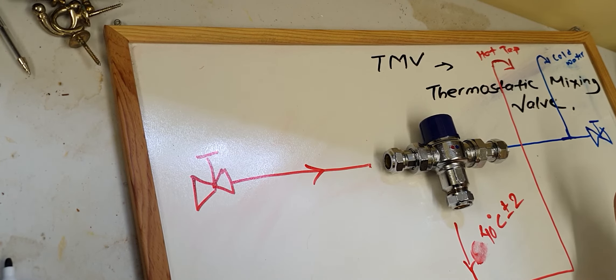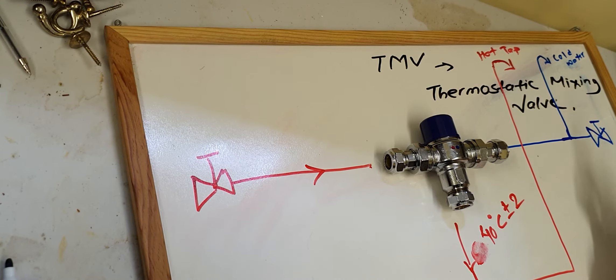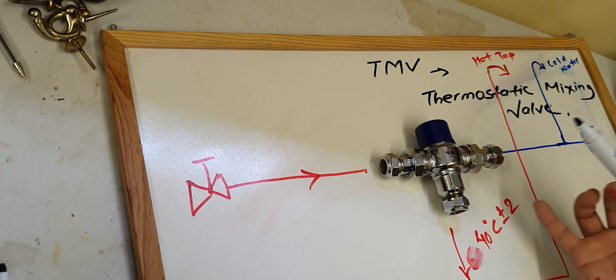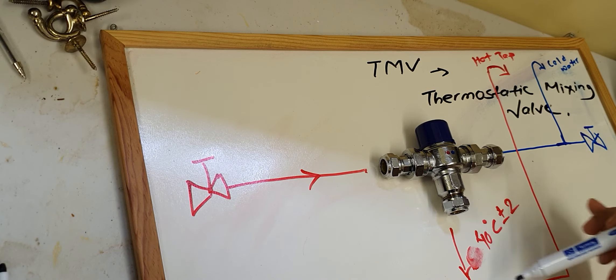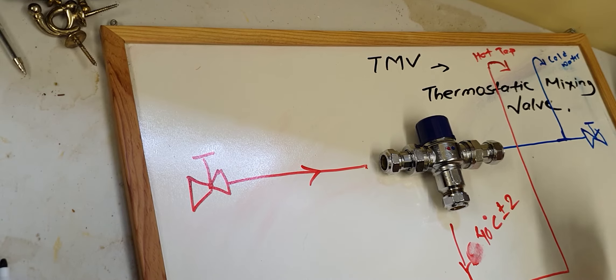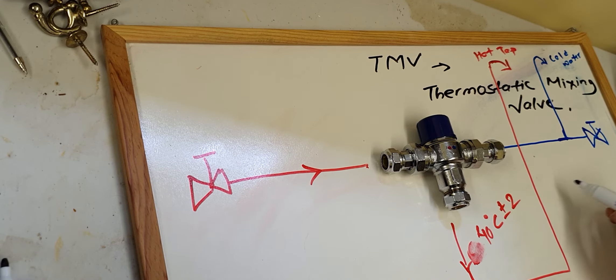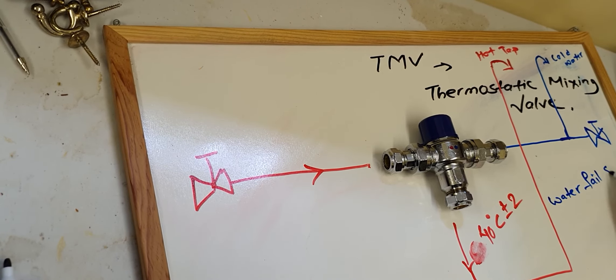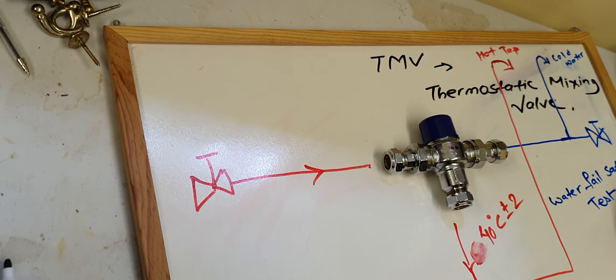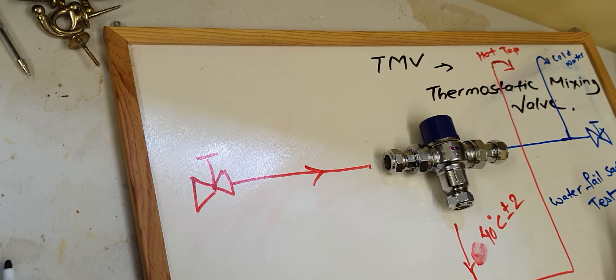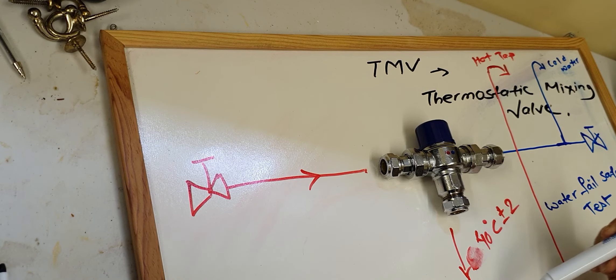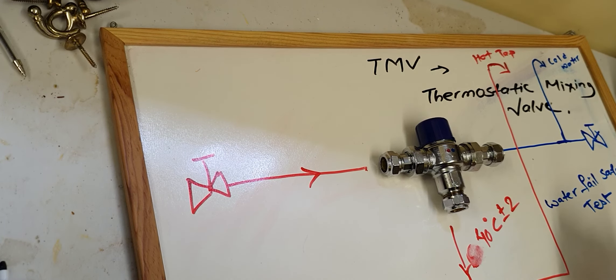You might be thinking, what if the cold water is off or if there isn't any cold water? What will happen to the TMV? Will really hot water come to the tap? No, it doesn't. The TMV shouldn't pass the water. This is a kind of fail safe test. If there isn't any cold water supply to the TMV, there won't be any hot water coming out from the hot water tap.